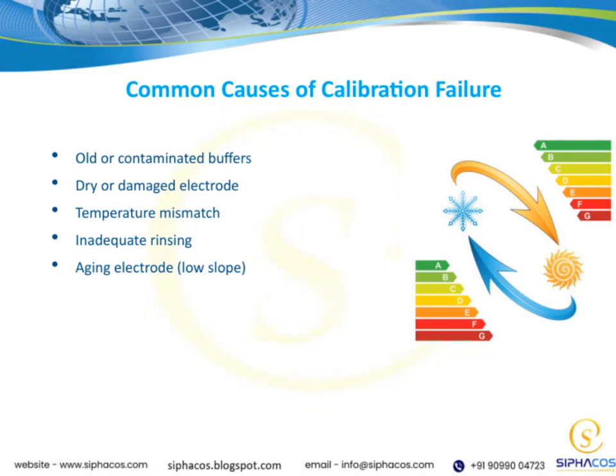Let's take a look at some of the common causes of calibration failure. First, old or contaminated buffers are a major issue. When buffers aren't fresh or have been contaminated, they can lead to inaccurate calibration results. It's essential to always use fresh buffers and store them properly.